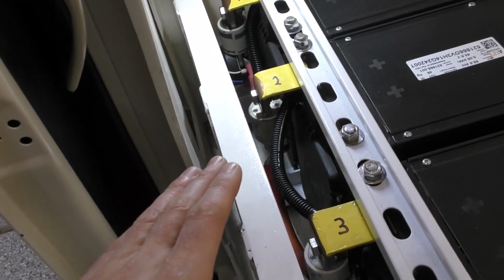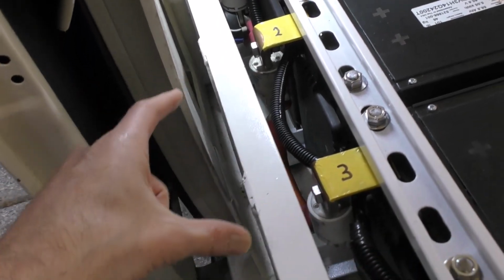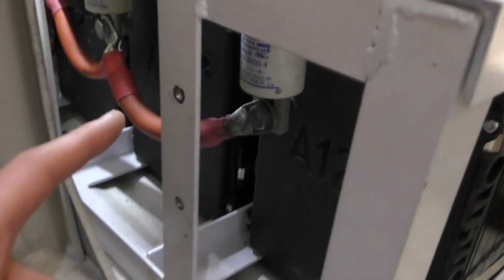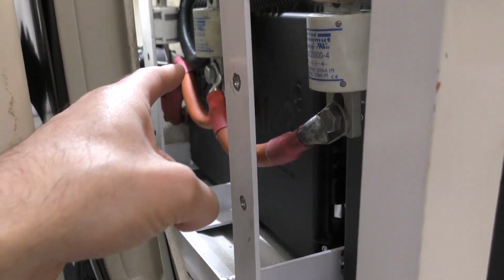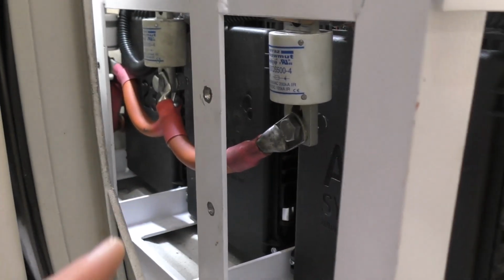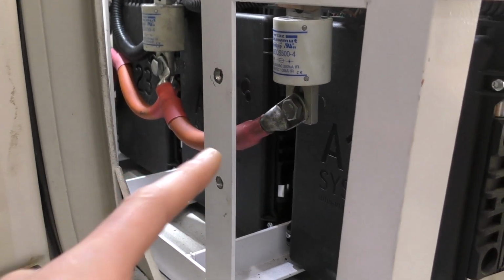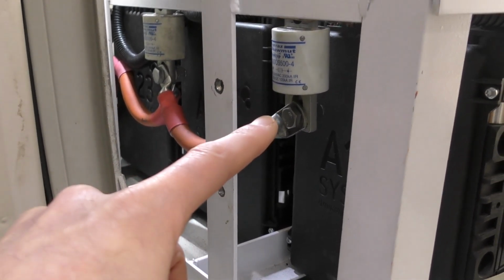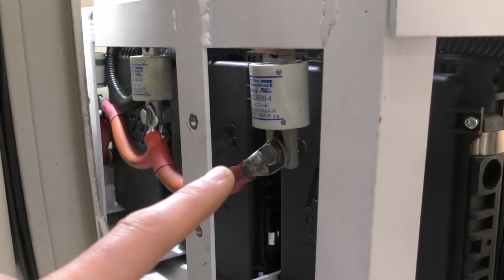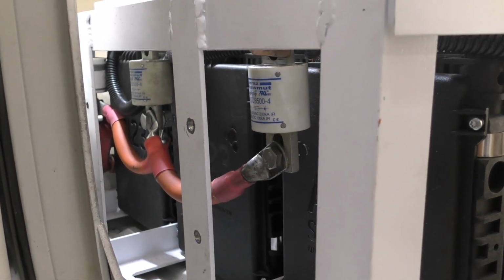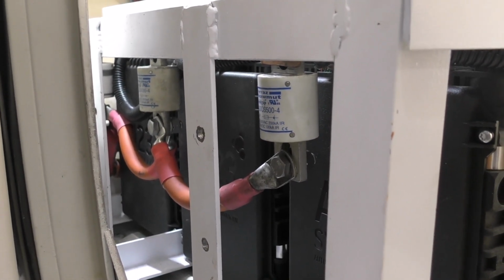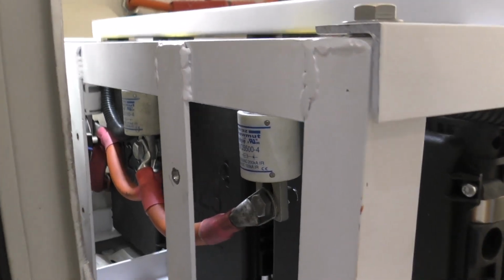Let me show you what I did. The big change to hardwire the packs was simply removing the contactors from my second and third pack. Now, as you can see, there's no more contactor, and I'm bridging right on the fuse. They still recommend separate high voltage fuses for each pack, but not contactors - just wired together.